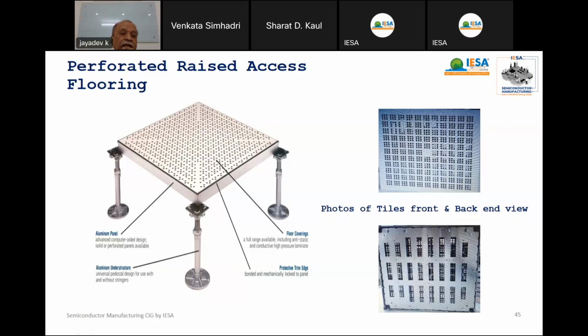Here they should be capable of taking the load of the process tools. In this case, they will take an ultimate distributed load of 100 to 150 kg force. Concentrated is 500 kg force. For ultimate load, the center of the tile can take 1250 kg. So that any process tool can be based on these tiles and they will take the load. This is the specification.